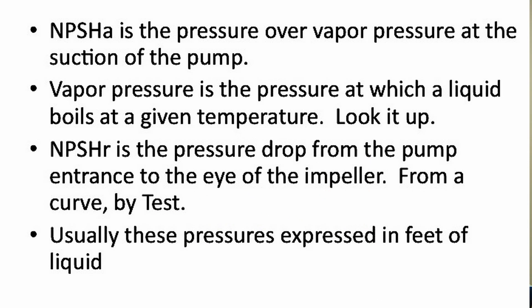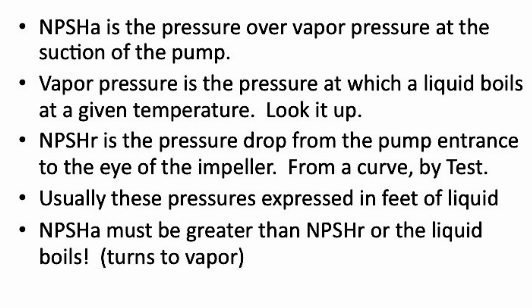NPSHA and NPSHR are expressed in feet of liquid. Obviously the NPSHA must be greater than the NPSHR, otherwise the liquid would form vapor bubbles in the eye of the impeller.